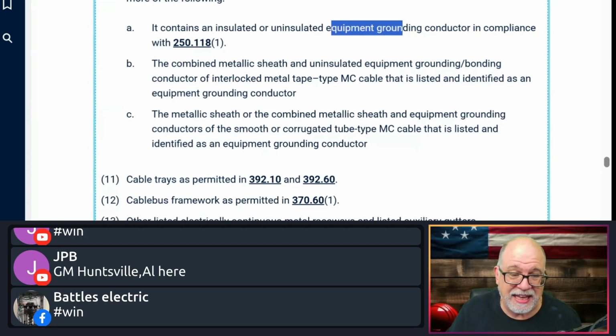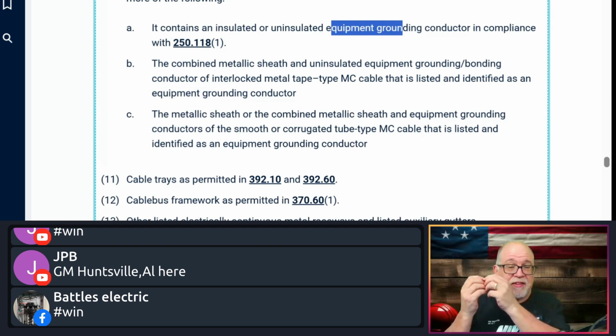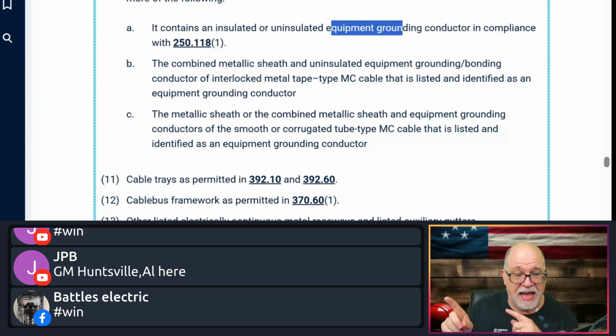That's the wire. Okay, so you can have a conductor in there. It can be insulated or uninsulated. A lot of people have a misconception about that. Most of the time when you see an insulated equipment grounding conductor, it's something like when you're doing healthcare facility, where you have an MC that's the HCF version, which has the armor as the smart ground. So it has this 10 gauge aluminum grounding/bonding conductor in there. And then inside of the bundle, it also has an equipment ground, but it is insulated because that is required by 517.13(A) and (B). Okay. But in normal MC, that equipment ground could be bare or insulated. It's basically up to the manufacturer.